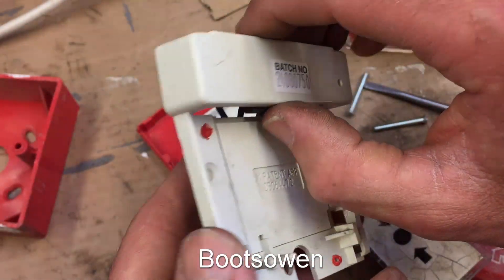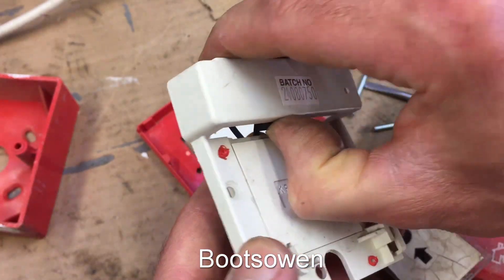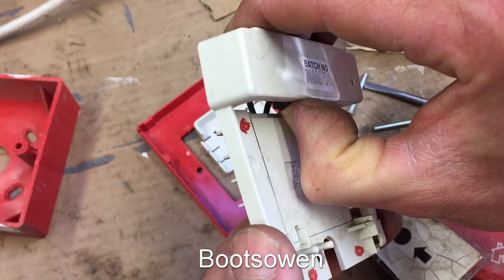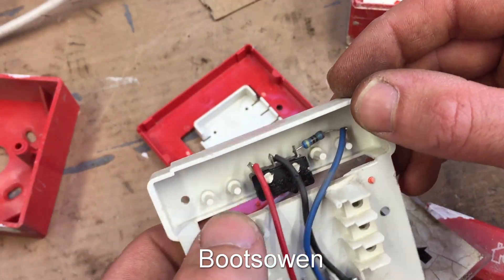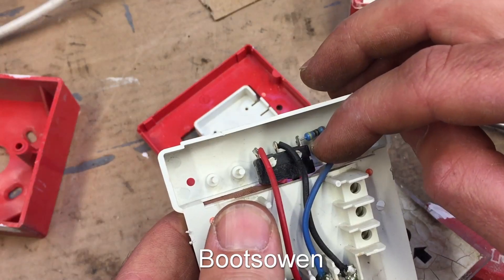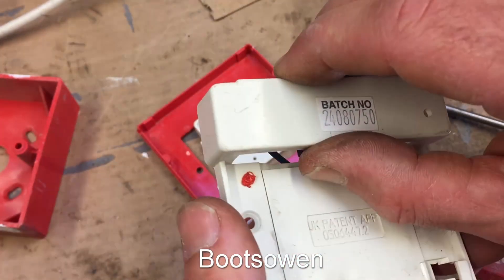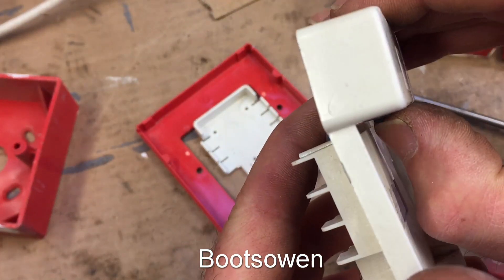All this is a switch and the switch is on. There's continuity whenever the glass is intact. When someone breaks the glass the switch pops out, breaks the circuit and the fault is detected — although it's a three-way switch, so maybe it switches over to the other side whenever the glass is broken. There's a change in condition whenever that switch is depressed — normally it's depressed.